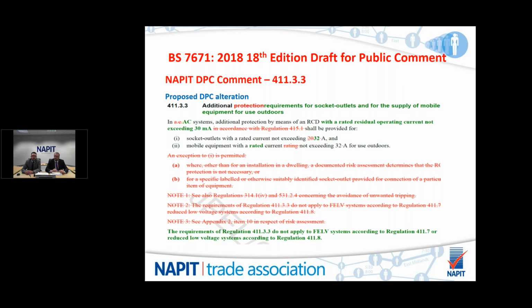411.3.3. Now, previously, you can see in the changes on the screen where it's green and red, where the red has been removed, the green are the new proposals for the 18th edition. So it states there is now additional requirements for socket outlets for the supply of mobile equipment for use outdoors. It's also added in there that it's a 30 milliamp RCD, not exceeding 30 milliamps. And the first of the bullet points has changed from 20 amps to 32 amps. So the rating of the socket outlets that have to be protected by an RCD has increased to 32 amps. And it remains that mobile equipment outdoors is still 32 amps.